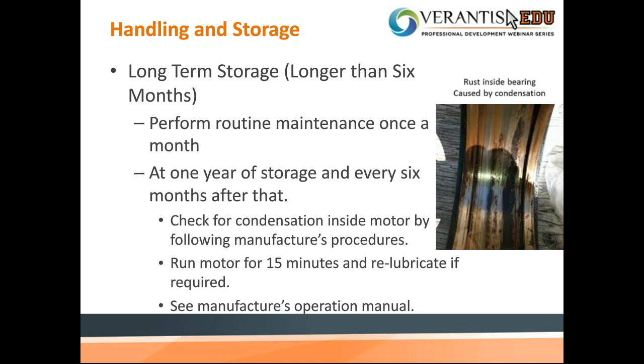With long-term storage, basically longer than 6 months, the routine maintenance needs to be performed once a month, just like we talked about for short-term storage. At 1 year of storage, and every 6 months after that, check for condensation inside the motor by following the manufacturer's procedure. If you can, hook up power and run the motor for 15 minutes to redistribute all the lubrication within the motor itself. That'll also redistribute some of the bearing grease as well. Also, like I said, I can't say it enough, see the manufacturer's operating manual. There's going to be some information that I'm sure I've even left out of this presentation that is going to be very specific for the model of fan that you have.